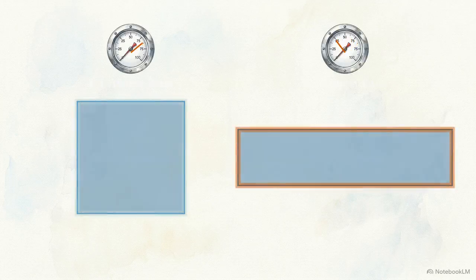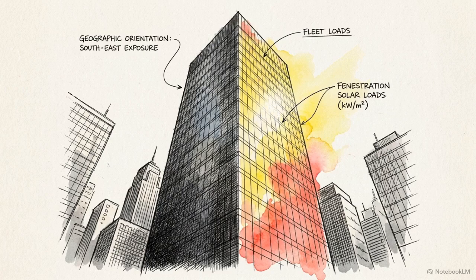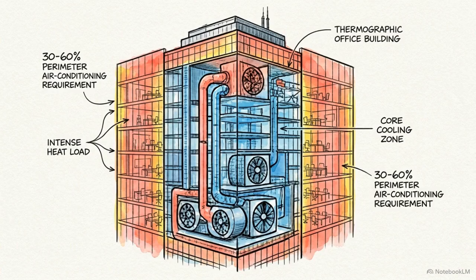Even with the same square footage, the aspect ratio of the floor plan drastically alters the required mechanical refrigeration load. A rectangular building with a 4:1 aspect ratio has a much longer boundary line, exposing significantly more perimeter area to the weather than a square building. That perimeter exposure is amplified by the building's geographic orientation and its fenestration, the amount of light-transmitting glass used in the walls. When glass covers a large portion of the exterior, the perimeter load alone can dictate 30 to 60% of the entire air conditioning requirement.